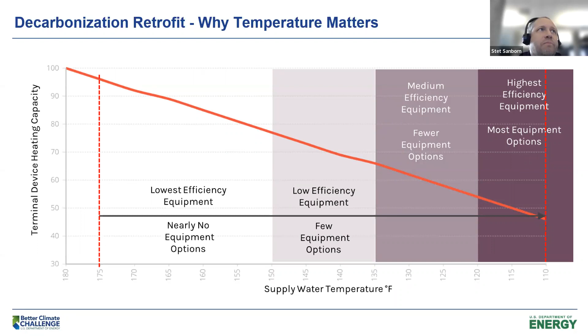We also trended the thermostats and tracked them to check at what point temperatures weren't able to be met, and made sure that winter season was deep enough to represent a typical winter. The further right you can go, the lower the water temperature you can achieve, the more options you'll have for which heat pumps and manufacturers you can work with. More heat pumps are serving higher temperatures now, but the bulk of them are better suited to low water temperatures. In this case, we were able to go from 180 degrees down to 150 with no problem, and we'll probably spend this year testing to see if we can go even further down.